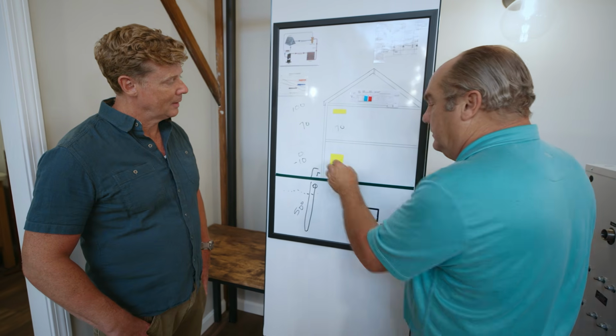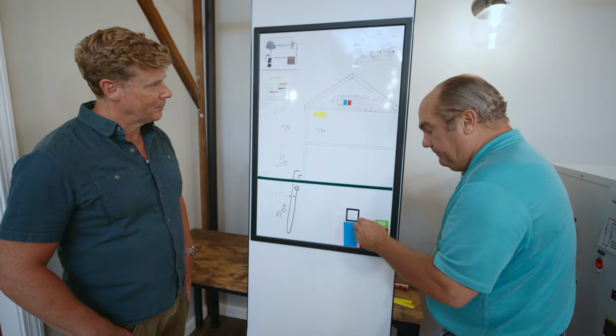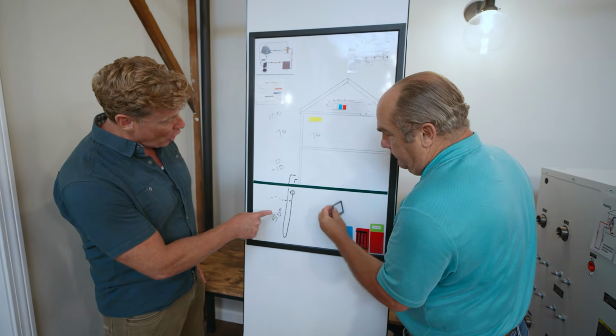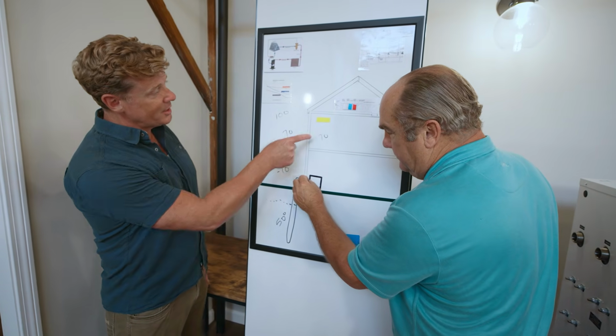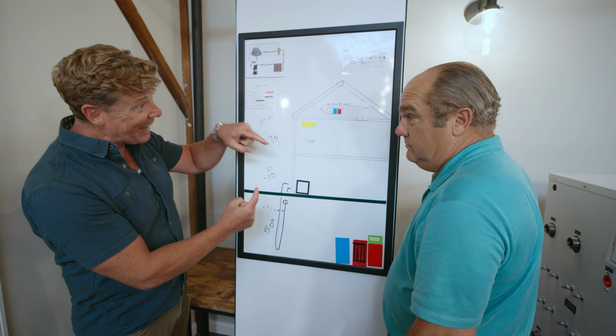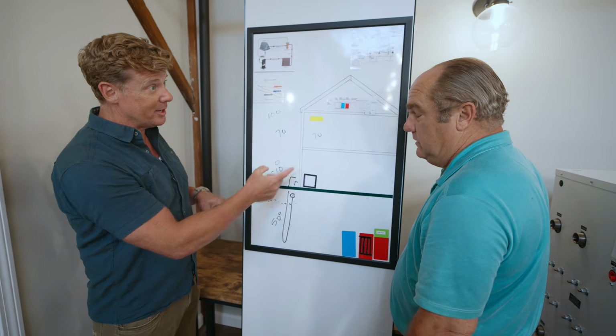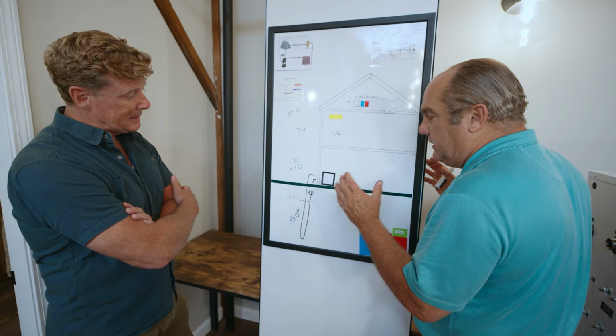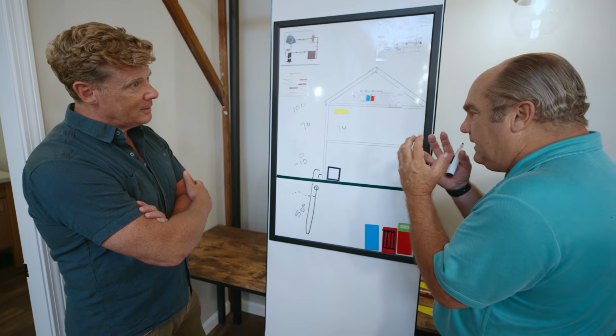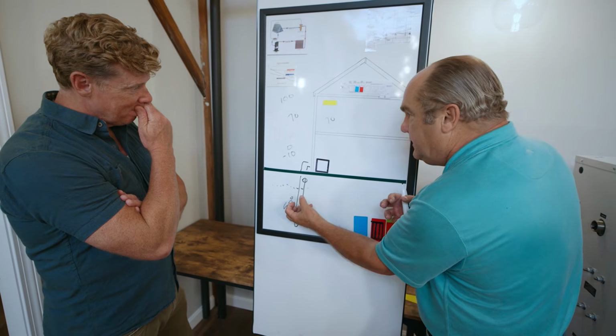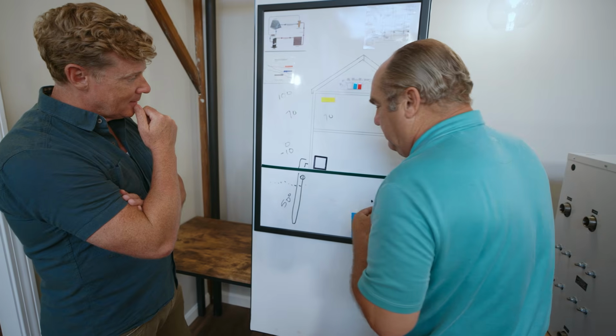Now inside the building, it would be a lot different looking unit. And so just so that I understand, going from 50 degrees to 70 degrees, moving that 20 degrees, is a lot easier than moving the 80 degrees here, so this is good. And that's really the key to it, Kevin. We're trying to move heat. We're not trying to make it, we're trying to move it, and so we can find the 50 and easily pump that thing up to get the building to 70.